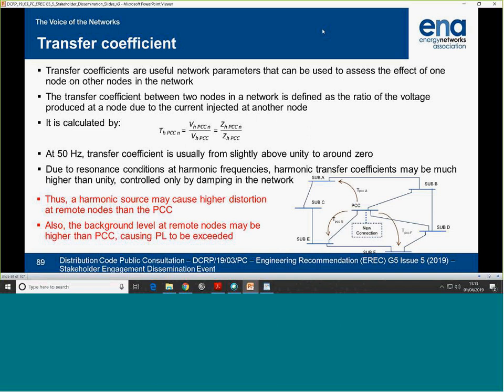Therefore, you may have a compliant PCC while the level at other nodes may exceed the planning level. That's why you need to look at remote nodes. The figure here shows what I said in words, in a diagram. Basically, you're connecting a connection there, with transfer coefficients to other nodes, which are determined from the network parameters. They tell you if you have X level here for a given harmonic, what would be the impact at other nodes?